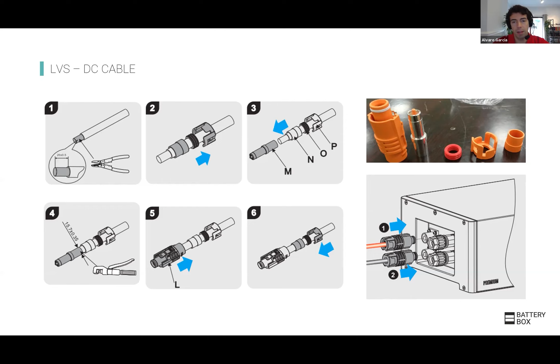When you parallel them, the two important things to take into consideration are, as usual, make sure the cables are the same section and same length for each of the batteries, and that at the end of the communication path, from the master battery, the out will go to the in of the first slave, and from its out to the in of the second slave. Make sure to put a terminator, a CAN terminator that is provided with the product, at the end of the line.